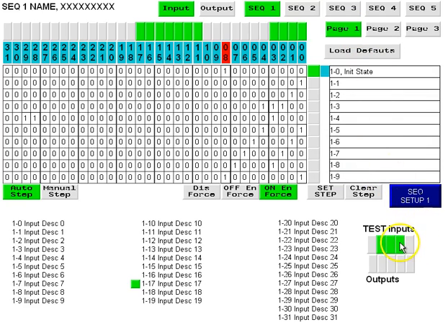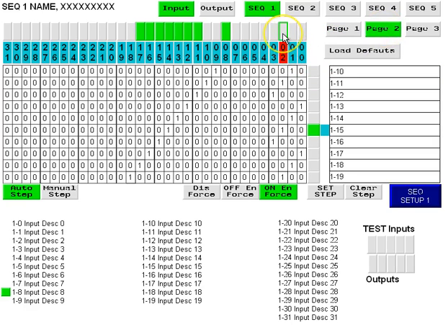Let's clean up a little bit, turn a few bits off. Let's turn bit 8 on by forcing. We're back to the beginning. State 0 wants to go to state 1 or to state 15. Let's select 15. Turned on. The bit, which was a run permit, was off, so it reverted back to 14.